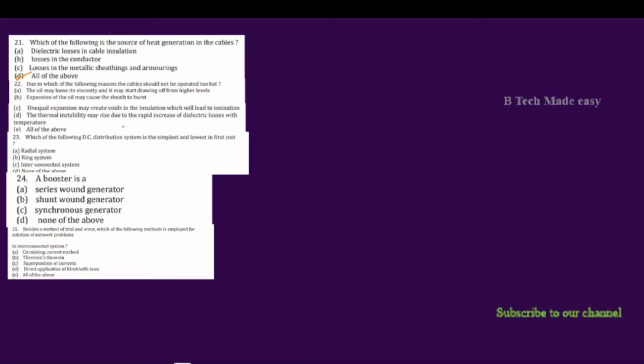The next question is: due to which of the following reasons should the cable not be operated too hot? The oil may lose its viscosity and start drawing off from higher levels — that is the correct option. Expansion of oil may cause the sheath to burst — correct. Unequal expansion may create voids in the insulation leading to ionization — correct. Thermal instability may rise due to rapid increase of dielectric loss with temperature — that is also a correct option.